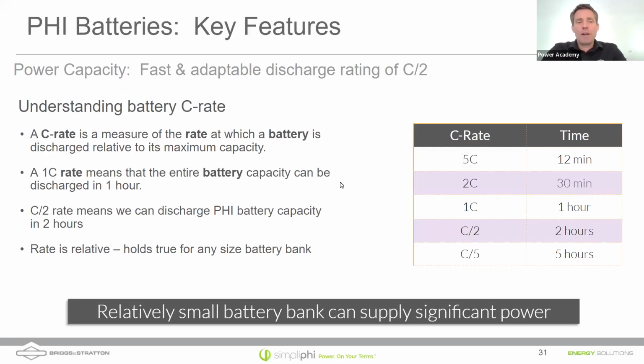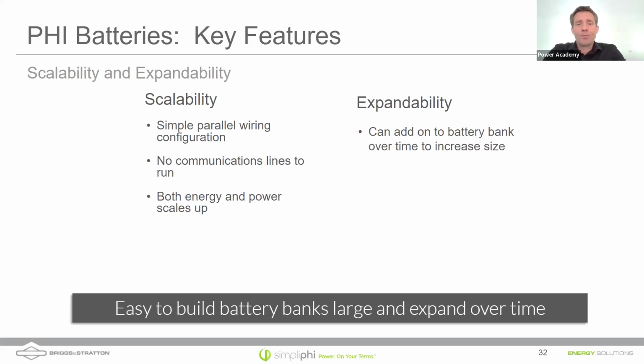The C rate of the batteries refers to how quickly you can charge and discharge them. Most of our batteries are rated at C/2. We have a new battery shipping next month with a higher C rate, up to 1C discharge, meaning you could use all of that energy in as little as an hour for a quick, high energy need. But most of our customers are expecting more like 5 to 10 hour discharge cycles.